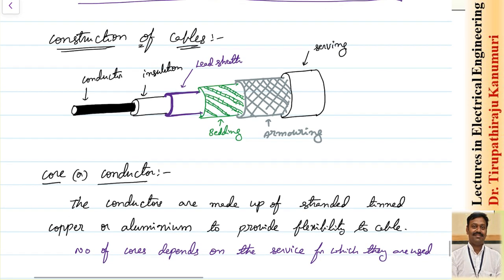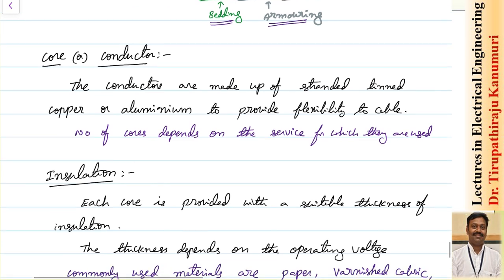The general construction of a cable consists of a conductor to carry current, surrounded by an insulating material. Above the insulation, a lead sheath is provided to protect against moisture absorption and mechanical damage. Above the lead sheath, a bedding layer is applied, followed by armoring which protects the cable from mechanical damage during digging or laying. Above the armoring, a serving layer protects against corrosion and rusting. Note that bedding and armoring may or may not be used depending on the application.